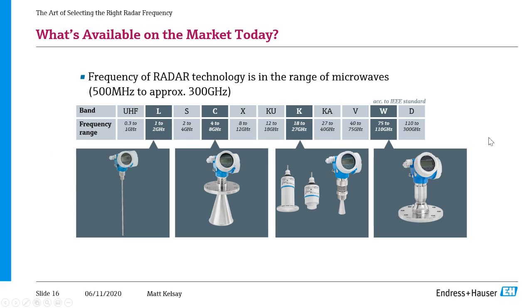All right, going to the next. From here on, I'm mostly going to cover radar devices. That's the bulk of the presentation, where we can get the most out of. So I want to take a second and look at what's available on the market today. Generally, they'll fall within 4 different frequency bands. Guided radar operates around 1 gigahertz in the L band. We have low frequency free space radars that operate in the C band, mid-frequency radars that operate in the K band, and then newer high-frequency radars operate in the W band.